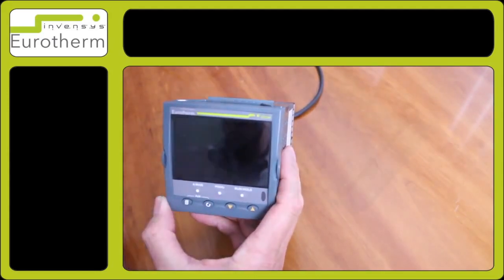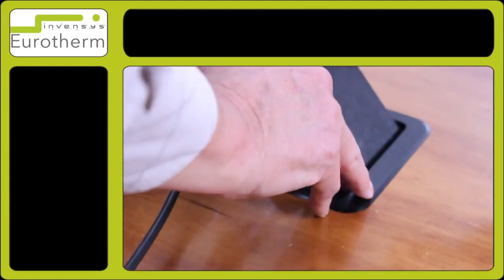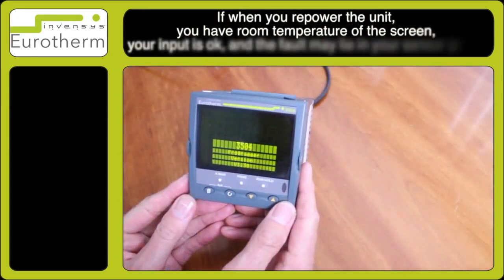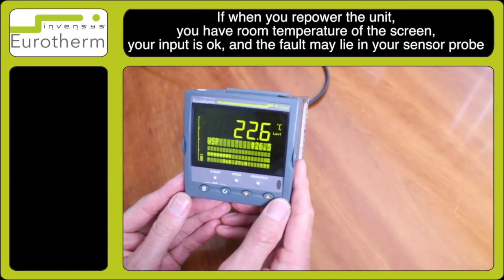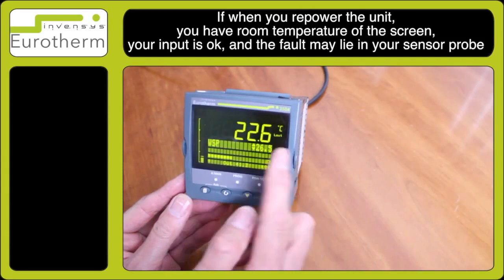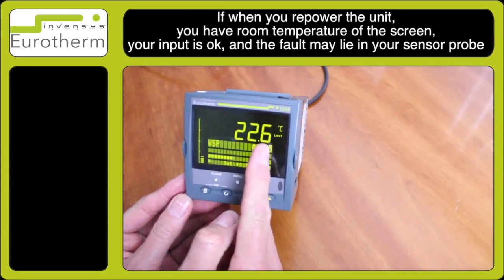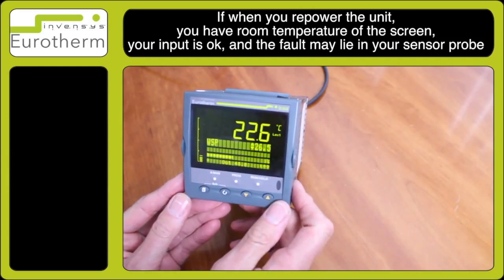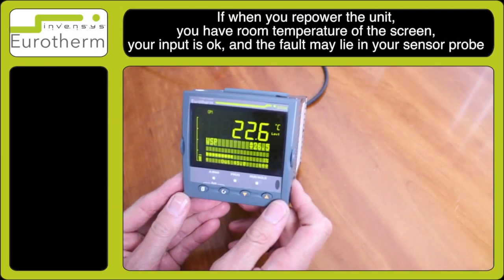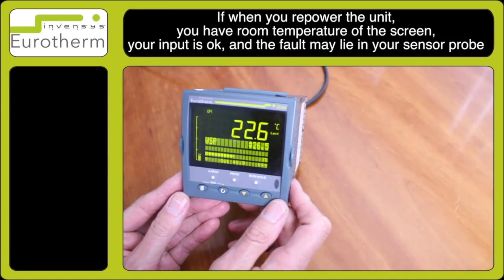Repower the instrument. After restarting, you will notice the instrument should show the room temperature. This normally indicates that the input to the controller is okay and the fault lies with your sensor probe.